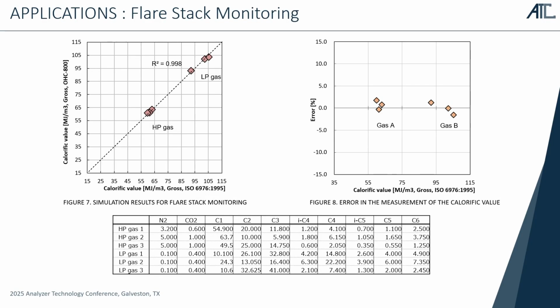All right, so more specifically about the flare stack monitoring. This is the test data that Rick and Keiki had for the flare gas application. There are two groups of gas, high pressure gas and low pressure gas, and each group has 3 target gases, and the gas components are mentioned here. But measuring these 6 gases, the accuracy, this is a theoretical calorific value, and this is a calorific value measured by the OHC 800. But there is a close measuring result. And then, as you can see here, the error is quite small.